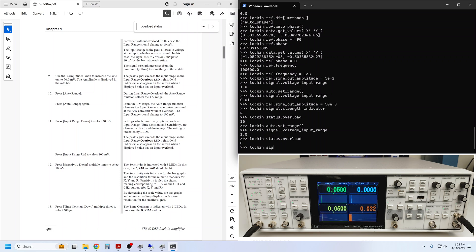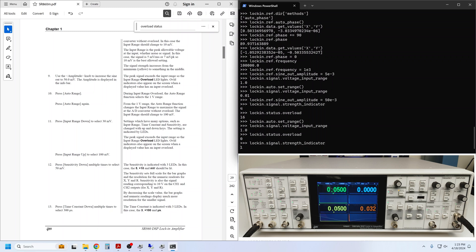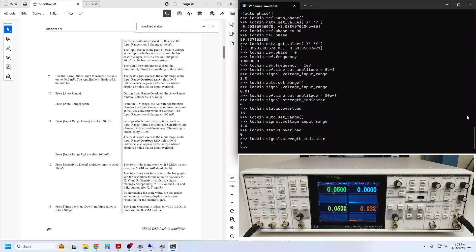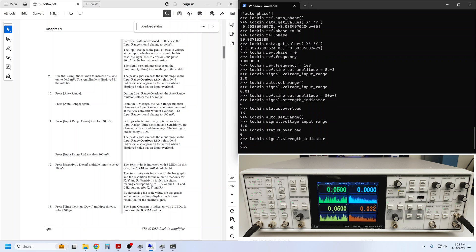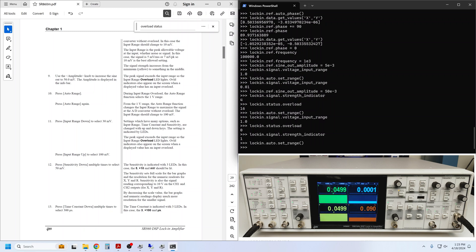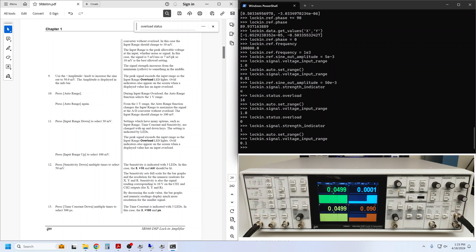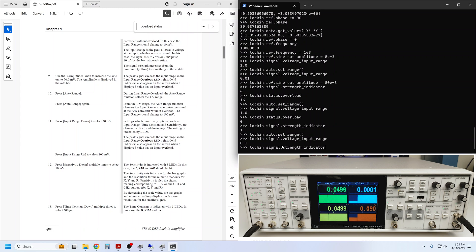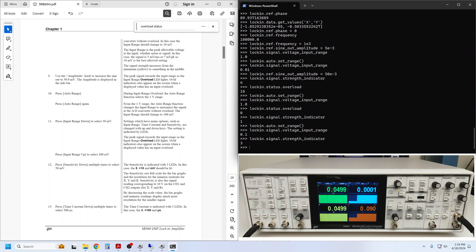We can check the overload status again, and you can see that the auto range did indeed resolve the overload, but using strength_indicator again, we can see that the signal is now not using much of the available range, so we are told to execute auto range again. This reduces the input range to 100 mV, which makes sense given our 50 mV excitation. And finally, if I can find signal strength, that is 3, meaning we are making maximum use of the input range without overloading.